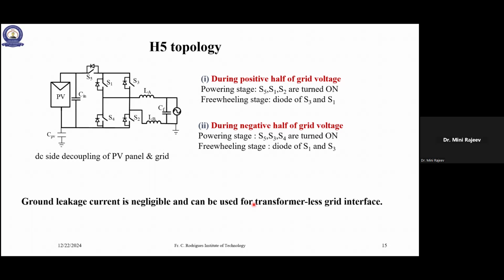So from this, what we can understand is that by modifying the single phase bridge topology in such a way as to make the common mode voltage constant, we can eliminate the leakage current. Another method is to short the grid and the PV directly so that the capacitor will not come into the picture. That I will show you.